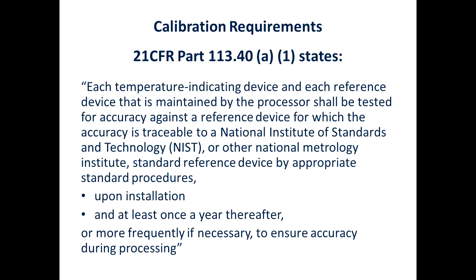And it states a couple things here. One, that the reference device you're using, which is your standard instrument when you're doing the calibration, has to be traceable to NIST or another metrology institute, and that you need standard procedures for this. They also state that it has to be calibrated upon installation and at least once a year thereafter, or more frequently if necessary, to ensure accuracy during processing. And that step really is completely up to you as the user.